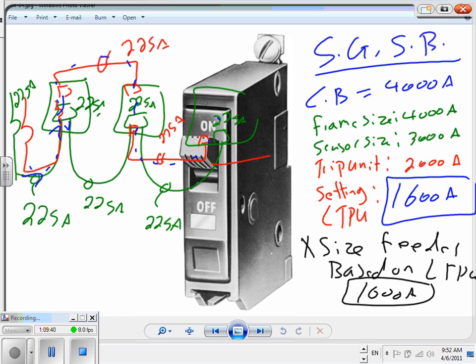We're coming with the software called SKM, guys. With SKM software, you're going to hear Chet talk about long time pickup, short time delay, and so forth. This is only with what we call adjustable electronic circuit breakers, not with these ones. These are dumber than rocks. They don't do that. They're small. These are adjustable electronic circuit breakers: big circuit breakers with electronic equipment, sensors and so forth, and a brain.